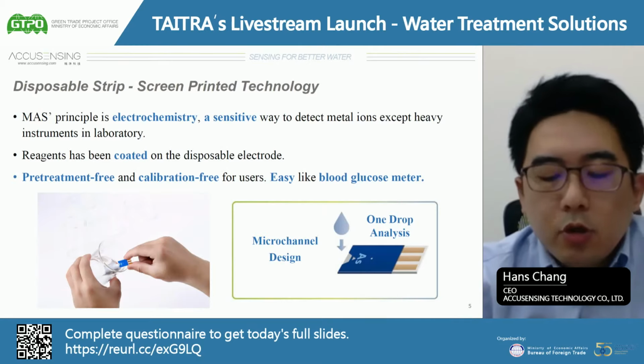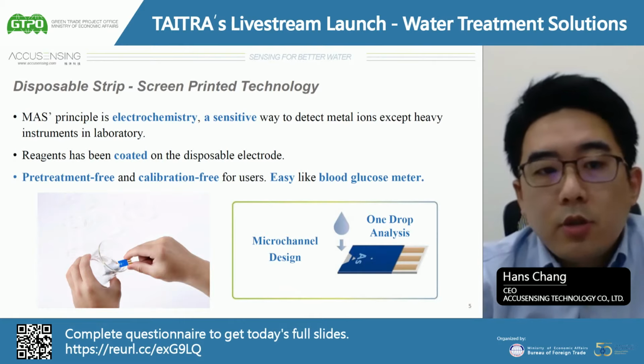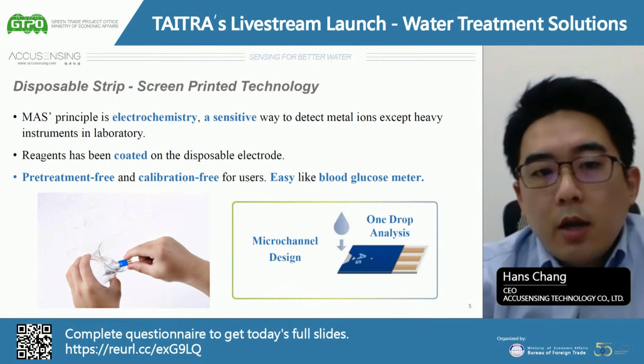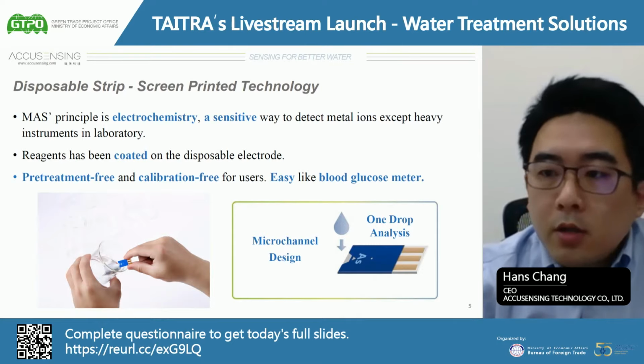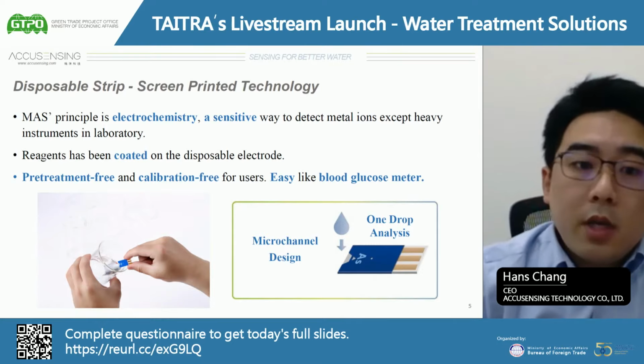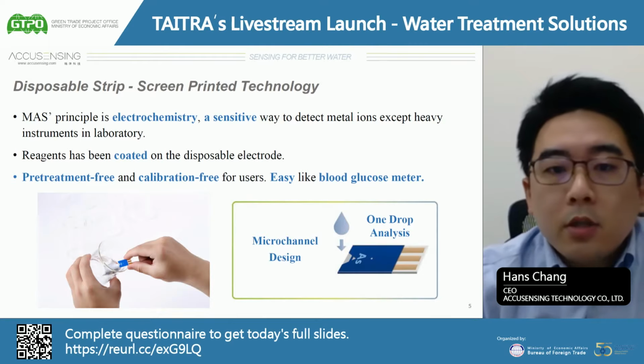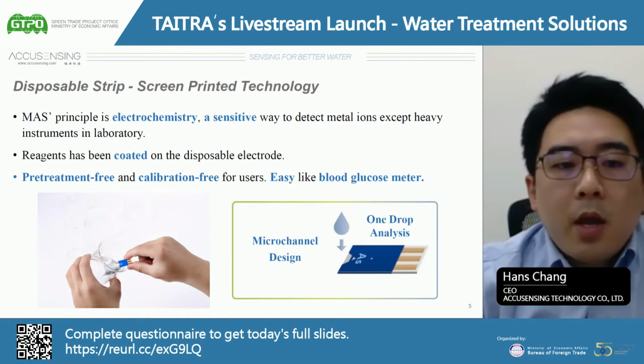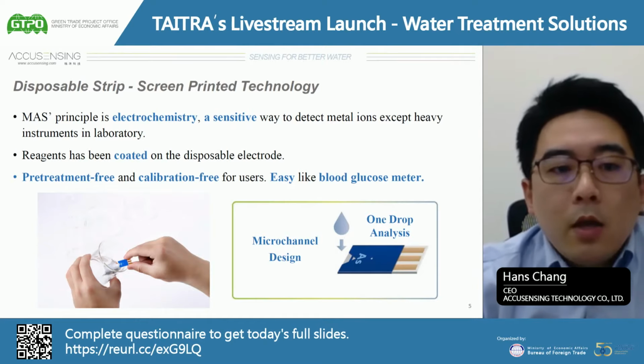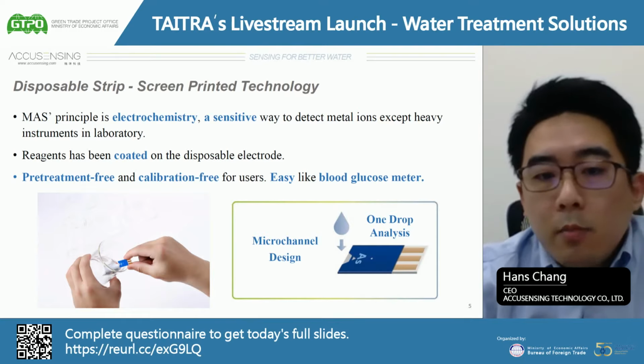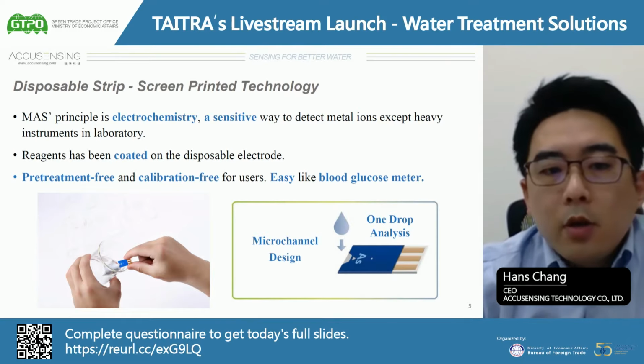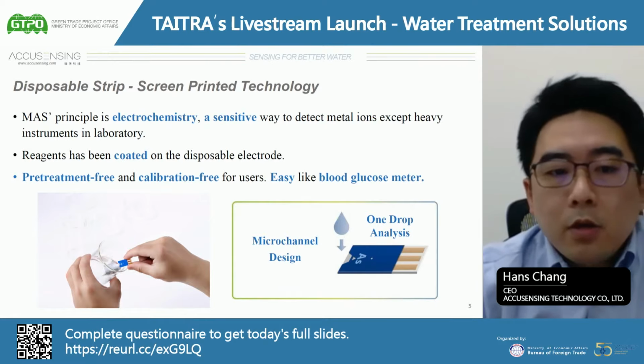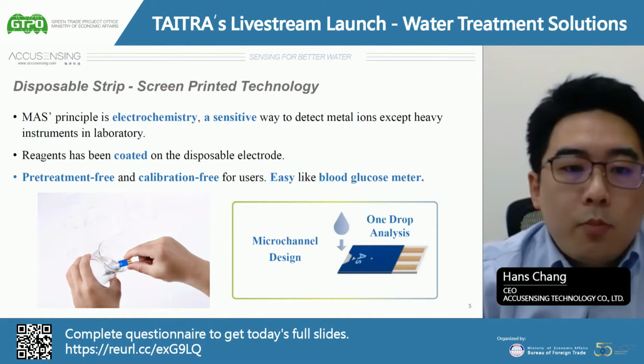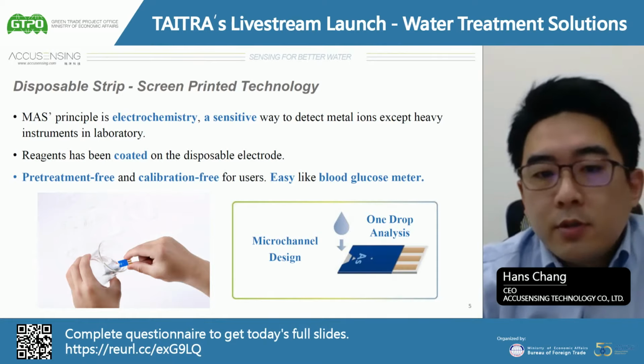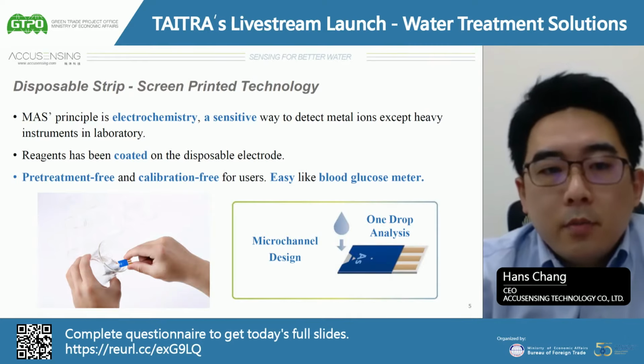Now I'm going to introduce our core technology, the disposable strip. Actually, it is an electrode made with screen printing technology. The MAS principle is electrochemistry, a sensitive method to detect metal ions, without the heavy instruments of a laboratory. The reagent has been coated in the microfluidic channel on the disposable electrode. Third, most importantly, it is pretreatment free and calibration free for users. So it is very easy to operate, like blood glucose meters. Next, please.